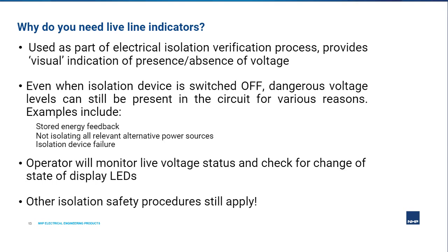When the isolating switch or circuit breaker is turned off, you can still have dangerous voltage levels present in the circuit. Coming into contact with it can be fatal. Why is there still dangerous voltage levels present despite isolation being performed? This could be due to a number of reasons. It could be due to stored energy feedback in the circuit. It could be because all power sources have not been correctly identified and isolated. It could also be that the isolation device itself has failed, and there are documented instances of this happening, and so energy is still supplied to the load. The bottom line here is that even if an isolating device is switched off, it's still not safe for the operator to presume that they can make direct contact with component surfaces.